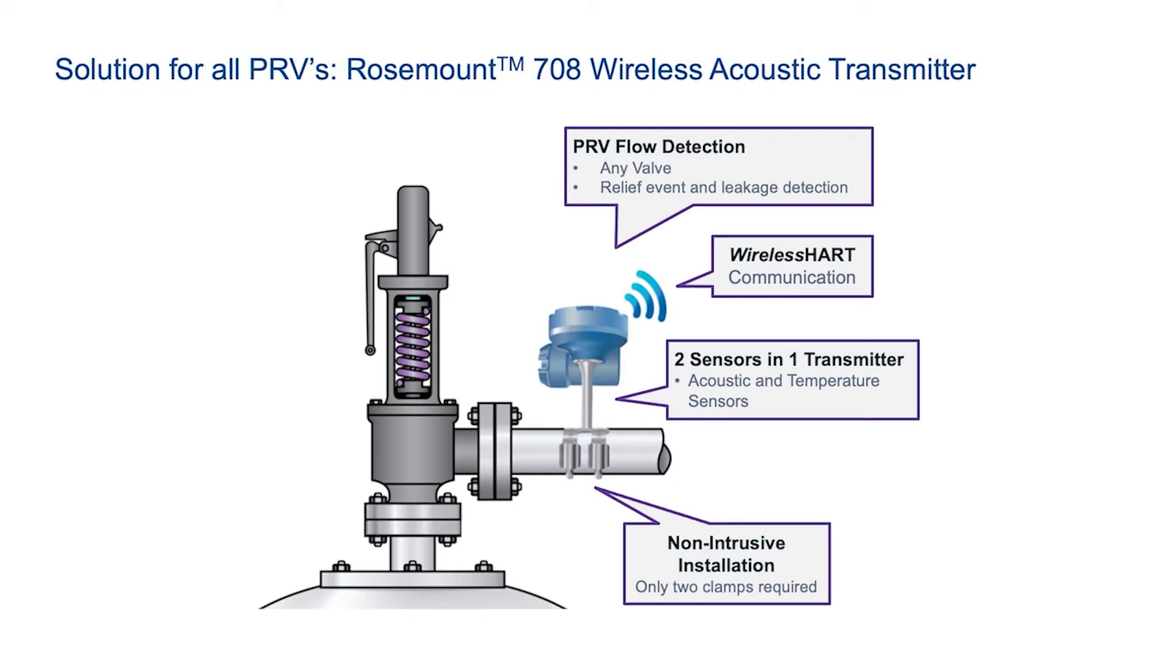The transmitter provides time stamp notification when the release is occurring and when the release has stopped. The Rosemount acoustic monitor is non-intrusive and can be directly mounted to piping without the need for cutting or changing piping and provides for a flexible and easy installation.